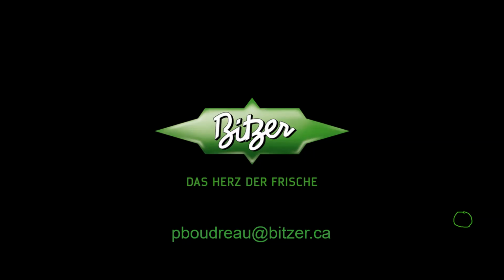Is there anything else to worry about when using a screw in low temperature? A screw compressor. Okay, that's a different topic altogether. However, screw compressors would require oil cooling when you get into low temperature applications. That's the main thing, because you're using oil to compress the refrigerant in those cases. So we want to make sure that our oil is not continually overheating. You want to keep the oil temperature within the operating requirements that BITZER has in order to keep the discharge temperatures in check.